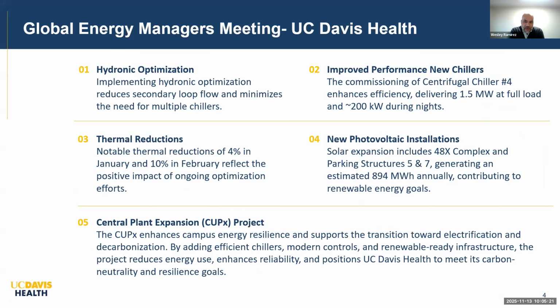I have 6 major points. First is hydronic optimization. As part of our master plan to meet seismic compliance for hospitals, we were able to hydronically separate our north and south wing, roughly 600,000 square feet of hospital, from the campus loop. That building was originally built in the 1920s, so it's time for it to go away, and we're building our replacement tower now. This separation let us significantly drop our minimum flow in the secondary chilled water loop, allowing us to turn off some of our larger 700 horsepower pumps in the central plant. With fewer chillers operating while maintaining campus cooling, we've improved efficiency.